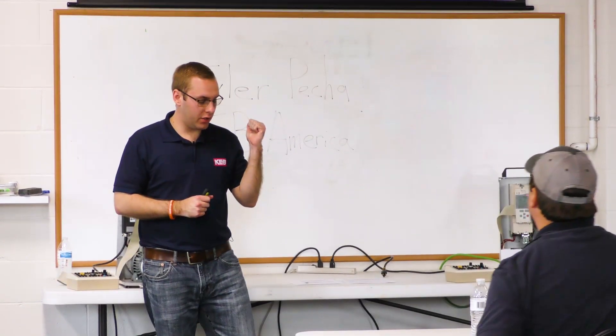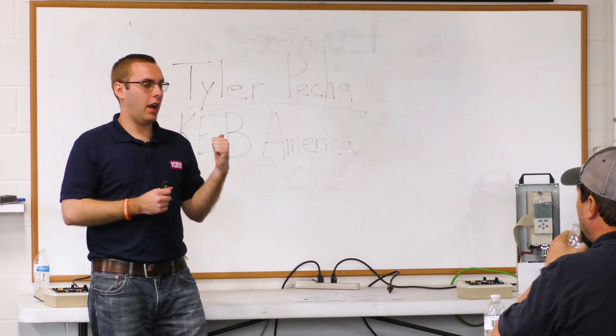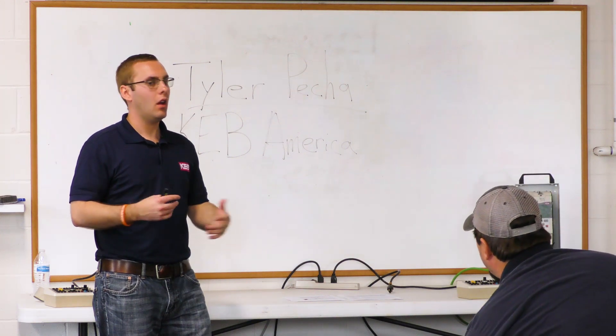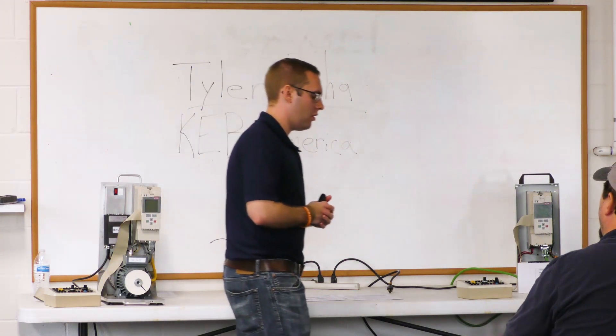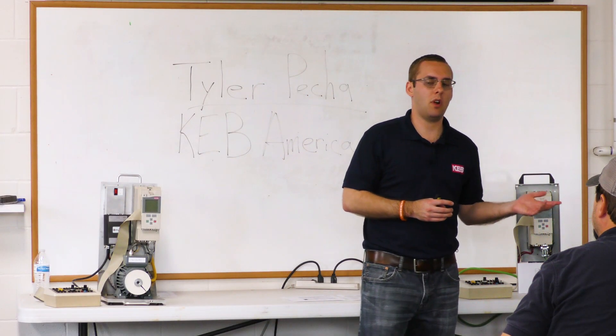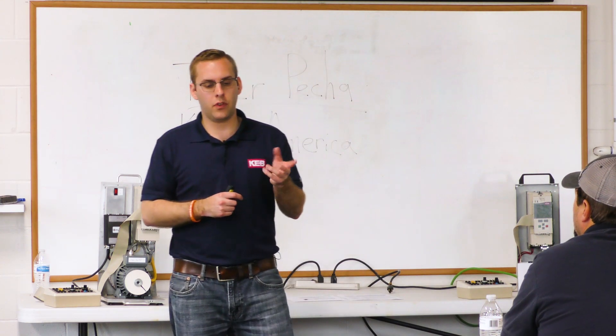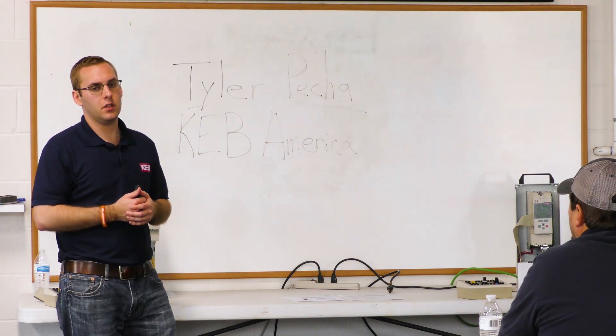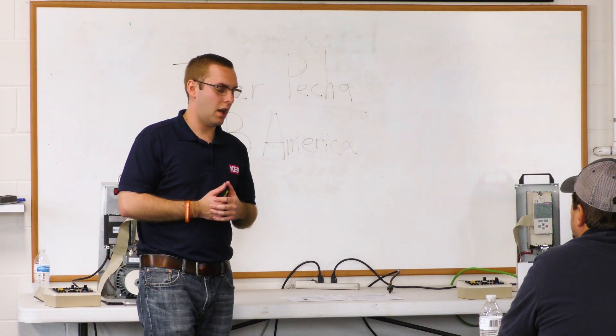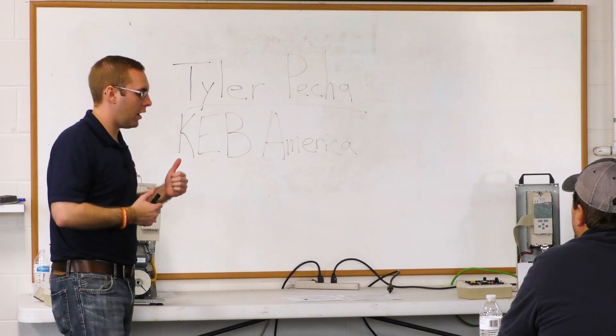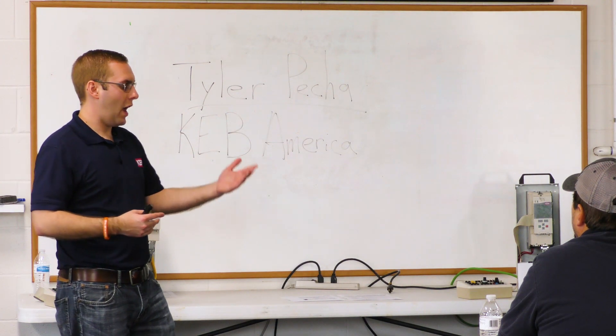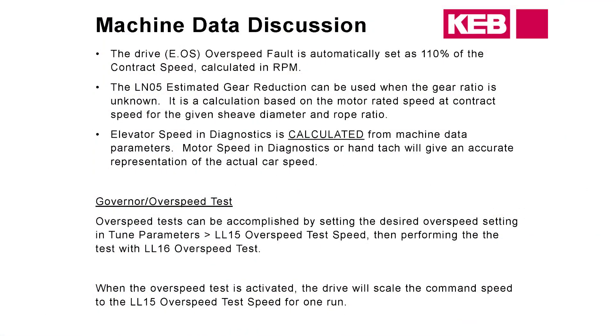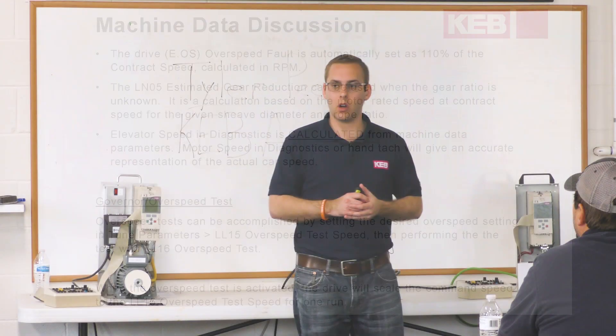For the overspeed test, we have a tune parameter set just for the governor overspeed test. What that allows you to do is avoid changing any parameters — so if you're running digital or binary speed control, you wouldn't have to change the gear reduction ratio to trick the drive into running faster. You would go to LL15 under the tune parameters and start an overspeed test. What that does is automatically bypass the 110% threshold in the drive, allowing you to overspeed the car for one run.